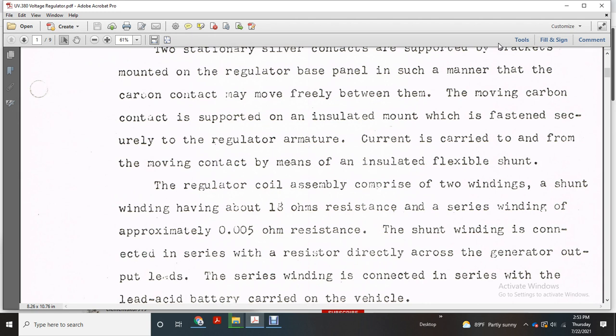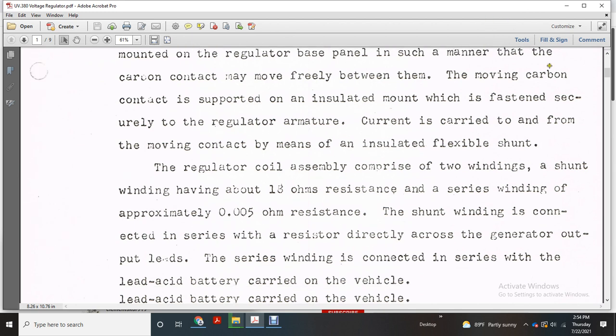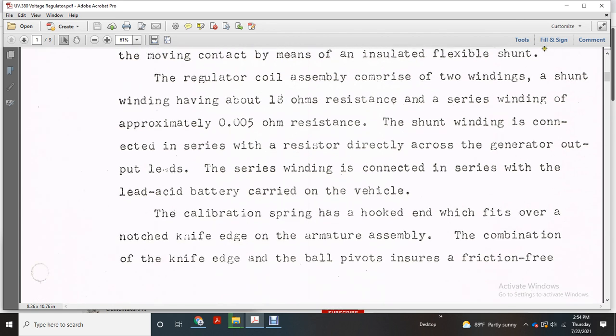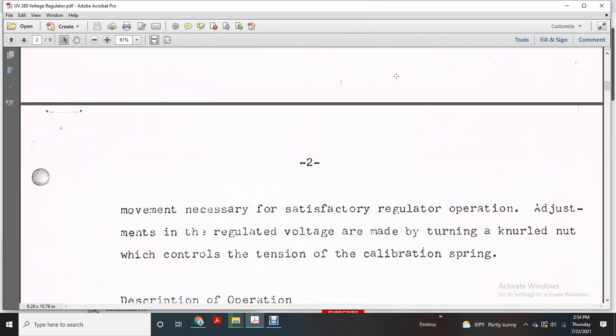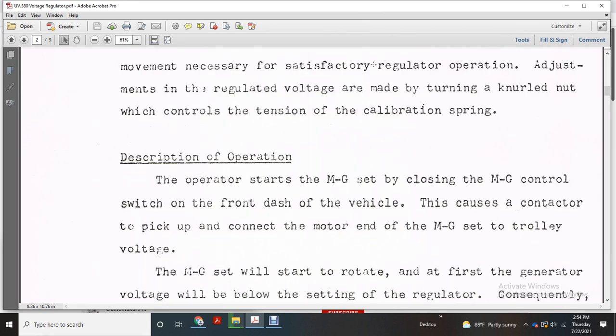The regulator coil assembly comprises two windings, a shunt winding having approximately 13 ohm resistance and a series winding of approximately 0.005 ohm resistance. The shunt winding is connected in series with a resistor directly across the generator output leads. The series winding is connected in series with the lead acid battery carried on the vehicle. The calibration spring has a hook which fits over the notched knife edge of the armature. The combination of the knife edge and the ball pivots ensures the friction free movement necessary to satisfactory regulator operation. Adjustments to the regulated voltage are made with the knurled nut, which controls the tension of the calibration spring. Description of the operation.